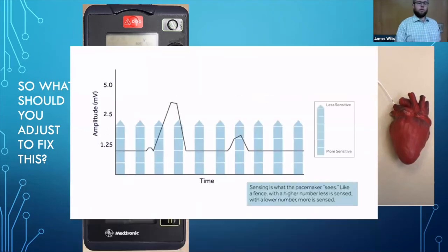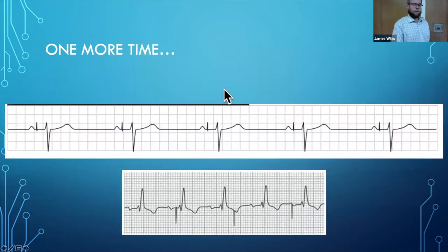In this situation, what we need to do is, it's seeing too much electrical activity, right? Our threshold is a little bit too low. We actually need to decrease our sensitivity, make that fence taller, so that the electrical activity that it's sensing isn't picked up and we can fire at the right spot. And then one last one. So what's going on here?